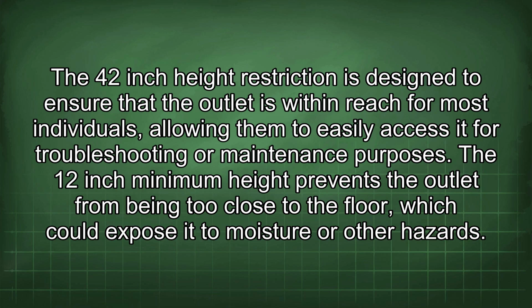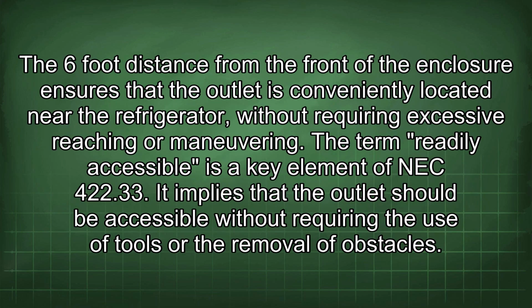The 42-inch height restriction is designed to ensure that the outlet is within reach for most individuals, allowing them to easily access it for troubleshooting or maintenance purposes. The 12-inch minimum height prevents the outlet from being too close to the floor, which could expose it to moisture or other hazards. The 6-foot distance from the front of the enclosure ensures that the outlet is conveniently located near the refrigerator without requiring excessive reaching or maneuvering.